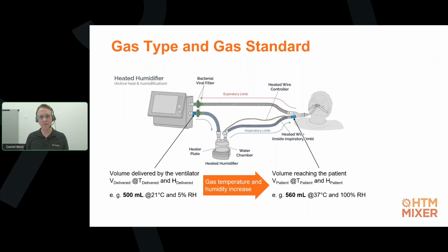So what ventilator manufacturers usually do is compensate for that with their setting and monitoring values on their devices, as this can all be calculated through gas standard conversion. So in our example, the setting and monitoring value on the ventilator would typically not be the 500 ml delivered to the circuit system, but 560 milliliters that is actually going to end up being delivered to the patient, because they know that this is going to happen in a real-life scenario.